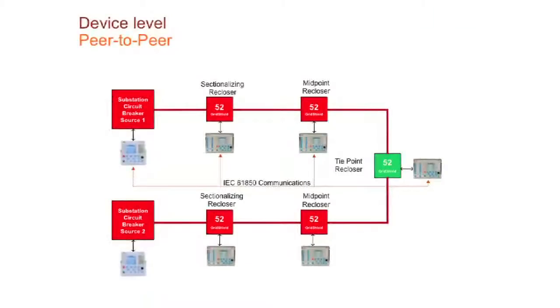So it's pretty much similar to GOOSE messages, but obviously you're sending through your DNP, or you're basically going back to a substation gateway to perform the logic instead of being peer-to-peer. This slide is just a screenshot of our DMS software. And the only reason I wanted to talk about this is because we talked about device logic. So device-level, peer-to-peer using GOOSE messages, substation-based using a communication gateway and a controller, or you can go to a centralized one.